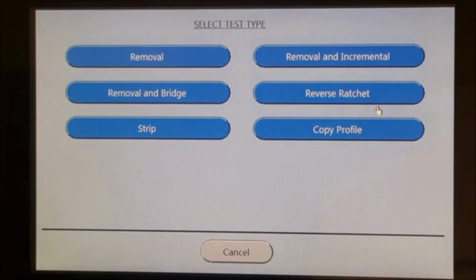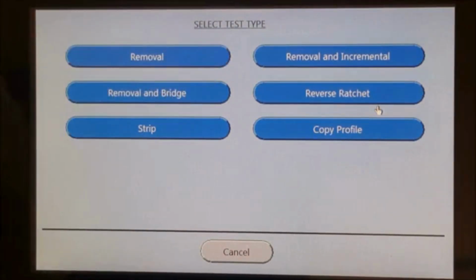The Removal test is a non-destructive test that is used to determine the peak removal torque of a cap. The removal torque is measured and displayed, and then the cap is reapplied to a specific value. The Removal and Incremental test is a non-destructive test used to measure the removal torque of a cap and then reapply the cap to a specified position beyond the original starting point. This test is designed to prevent leaking by reapplying the cap to a more secure position.